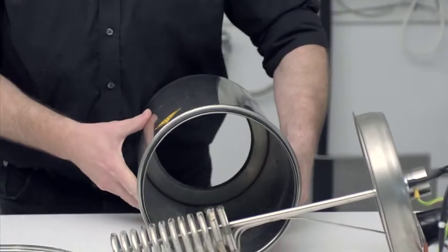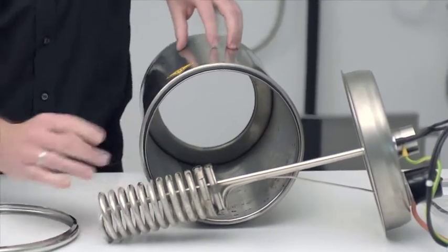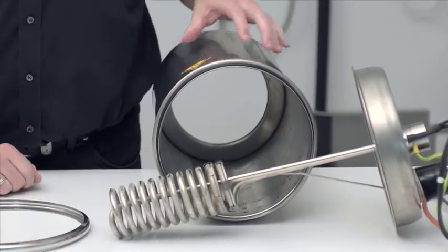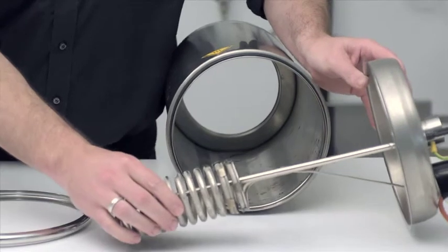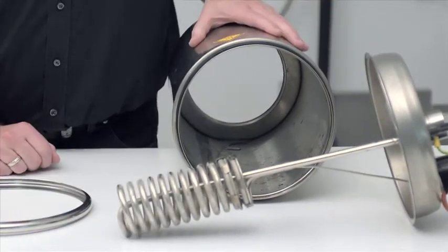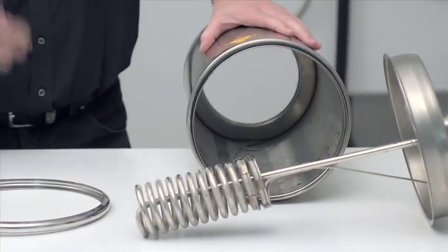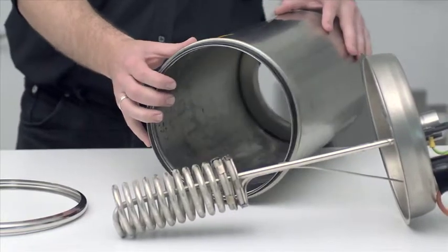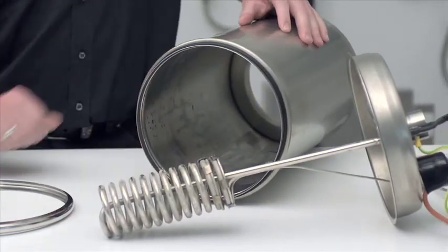You can tell that both the heating element and the cylinder still look very good. There is very little calcium residue. Normally you would find a little more which of course all depends on the length of time the steam humidifier has been in operation.